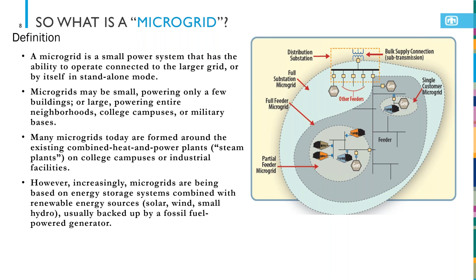Some of the key components of a microgrid: you have to have your own generation. Generators, combined heat and power, renewables, and energy storage are examples of a generator, as in the picture on the right. Energy sinks here are loads, typically residential or industrial loads. You have to have a means of connecting or disconnecting from the larger power system through a point of common coupling. You'll hear that, PCC. It's just an area where the microgrid itself can either connect to be grid tied, or disconnect into off-grid mode or islanded mode.